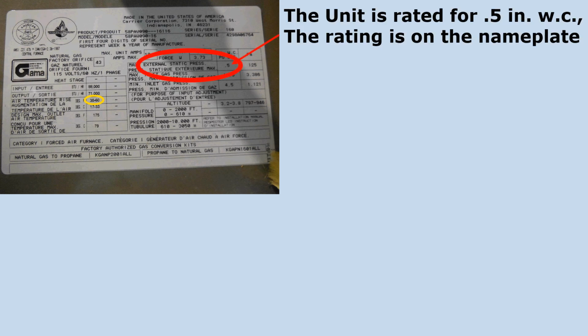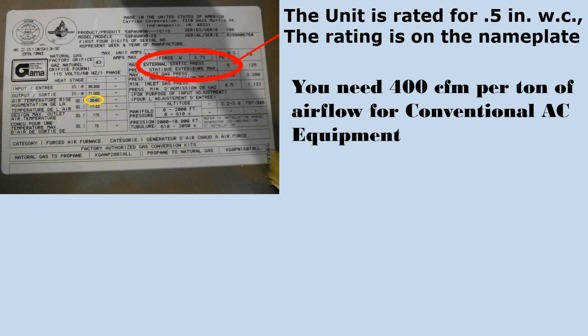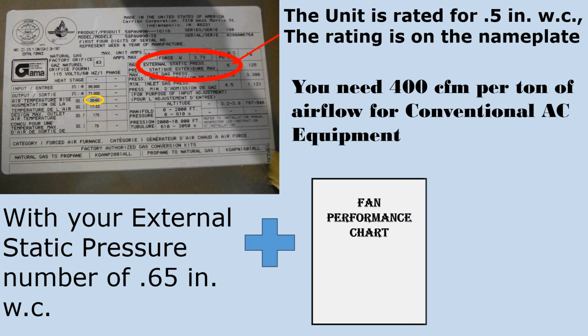The unit is rated for 0.5 inches of water column. The rating is on the nameplate. It's 400 CFM per ton of airflow for conventional AC equipment. And we're just talking AC here. I realize that we're talking about a furnace, but it would be the same, as you'll see here in a minute in the chart. With your external static pressure number of 0.65, plus your fan performance chart, you can get the CFM. And the fan performance chart is in the spec sheets, and now it's in the installation manuals of the equipment.